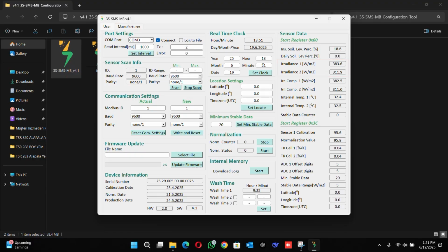Set the current time, date, and time zone based on your project's location. This step is very important, as any incorrect input would lead to wrong calculations of soiling ratio. The system uses a 24-hour clock. Once saved, the fields will turn green, confirming the input was accepted. If the values turn red, check for input errors or contact support.